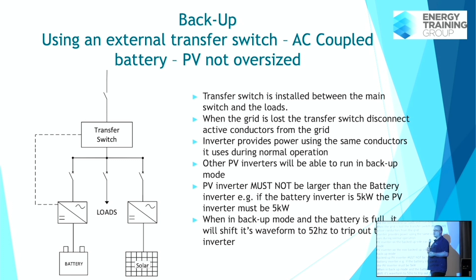There's nowhere for the excess current to go, so you've got to find a place for it to go. Generally if a customer wants a battery, they've usually got a few dollars. So they want a 10, 12, 13 kilowatt hour battery, usually connected to a 5 kilowatt inverter, but they want 10 kilowatt of solar. One way to get around that, especially if you're retrofitting, they've got existing 5 kilowatt, you're going to install your transfer switch somewhere in the board. So one of your inverters is on the backed up side of the transfer switch, and your other inverter is on the non-backed up side. And you're going to install 2 5 kilowatt inverters instead of 1 10 kilowatt inverter. So when we're in backup mode, this inverter can't overload this inverter. And when we're in backup mode, this inverter won't function. All right? I've seen that happen a lot of times where guys have thought, I've got a 5 kilowatt battery inverter, I can install a 10 kilowatt solar inverter, and then in backup mode, it doesn't function as they would like.